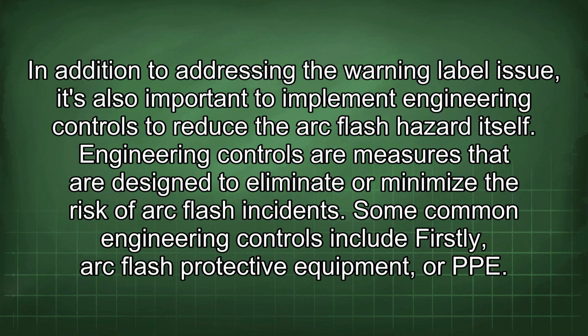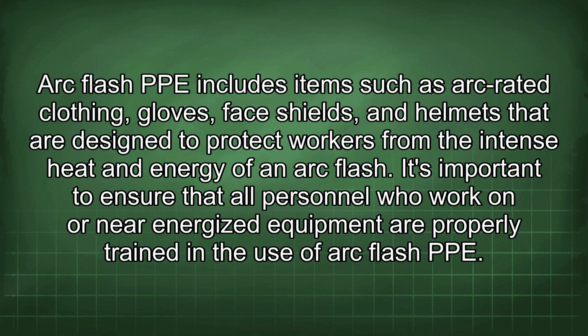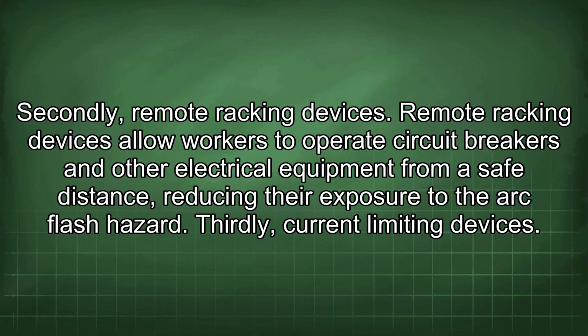In addition to addressing the warning label issue, it's also important to implement engineering controls to reduce the arc flash hazard itself. Engineering controls are measures that are designed to eliminate or minimize the risk of arc flash incidents. Some common engineering controls include, firstly, arc flash protective equipment, or PPE. Arc flash PPE includes items such as arc-rated clothing, gloves, face shields, and helmets that are designed to protect workers from the intense heat and energy of an arc flash. It's important to ensure that all personnel who work on or near energized equipment are properly trained in the use of arc flash PPE. Secondly, remote racking devices.